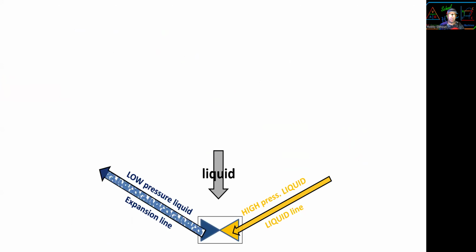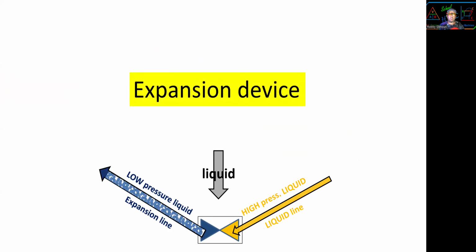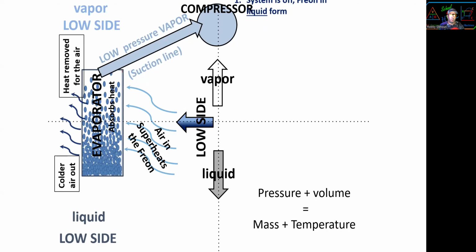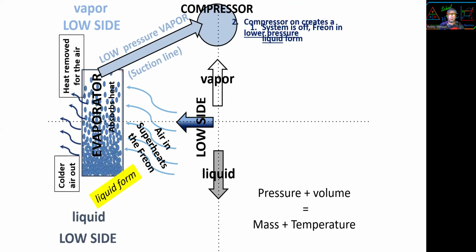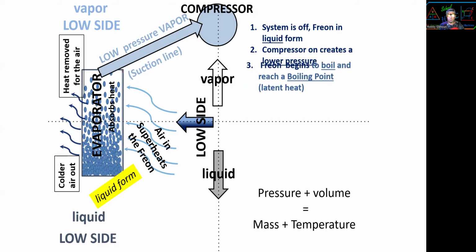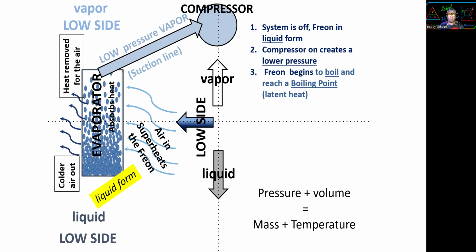Now, today is about TXVs. Metering device, or TXV, or expansion device: temperature and pressure decreaser. Alrighty, so the system is off. Freon is in liquid form. Then the compressor comes on and creates a lower pressure, a lower vacuum. Freon begins to boil and reach boiling point, and that's your latent heat. Now it is boiling, a liquid vapor mix. And by the end of the evaporator, it should be 100% vapor back to the compressor.